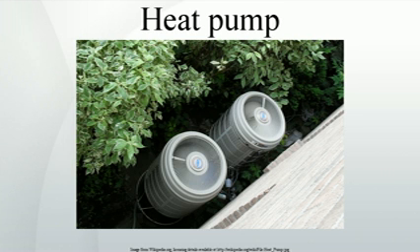Actual performance varies, however, and depends on many factors such as installation, temperature differences, site elevation, and maintenance. Heat pumps are more effective for heating than for cooling an interior space if the temperature differential is held equal. This is because the compressor's input energy is also converted to useful heat when in heating mode, and is discharged along with the transported heat via the condenser to the interior space. But for cooling, the condenser is normally outdoors, and the compressor's dissipated work, waste heat, must also be transported to outdoors using more input energy, rather than being put to a useful purpose.